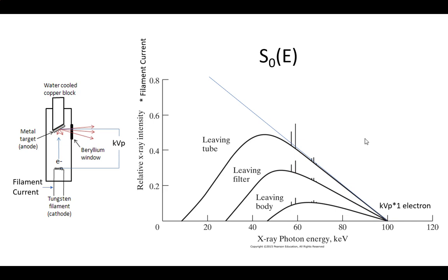So there's two things we really control, basically, when we do an X-ray image of something. We want to control the intensity of our source. That's controlled by the filament current. And so hopefully that now makes sense. All this does is just generate the electrons. So just think of it as a little coiled wire, tungsten, thermal heating, right? V equals IR stuff, that produces your electrons, away you go. Right? Pretty linear in this stuff.